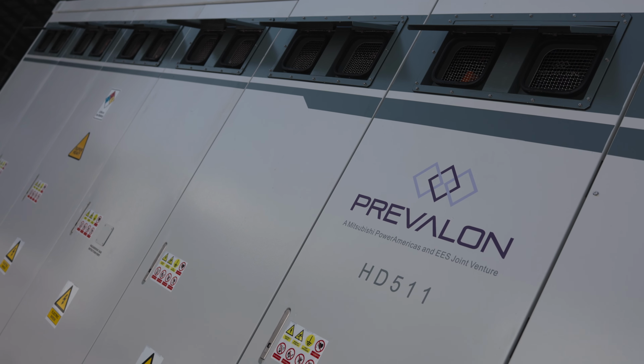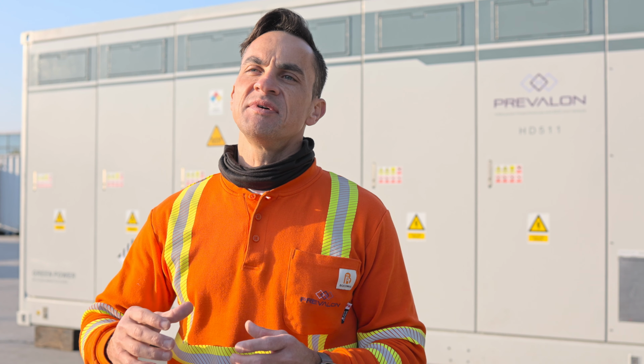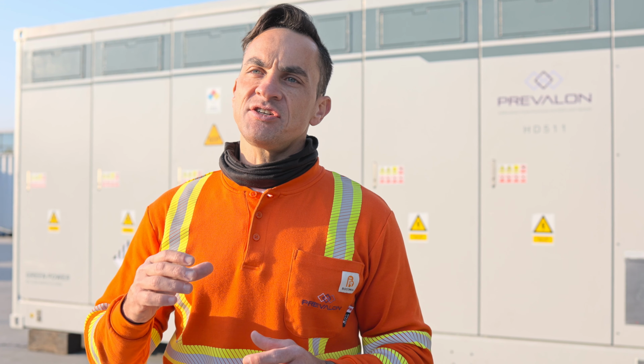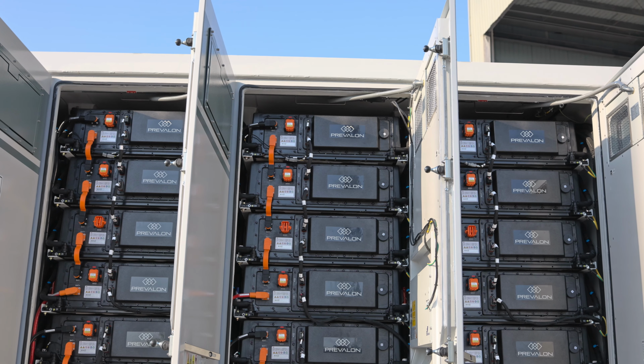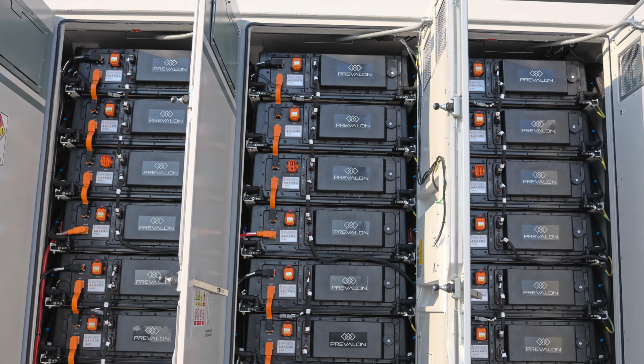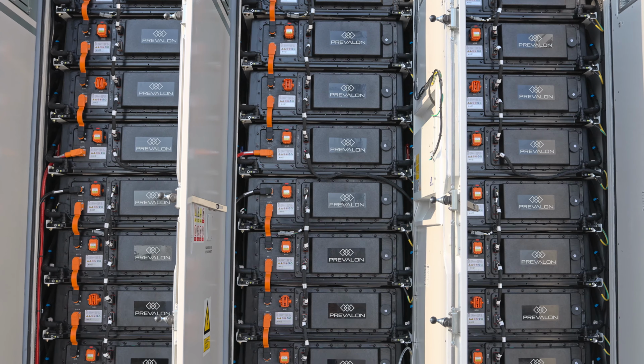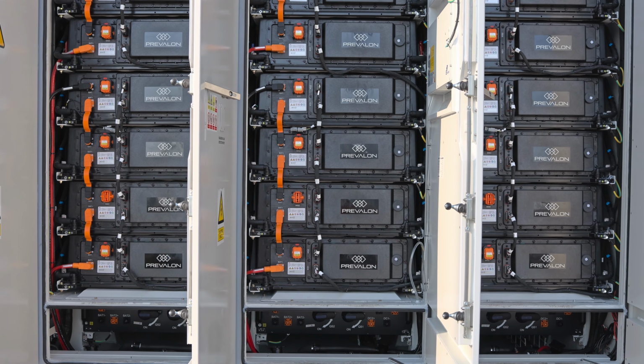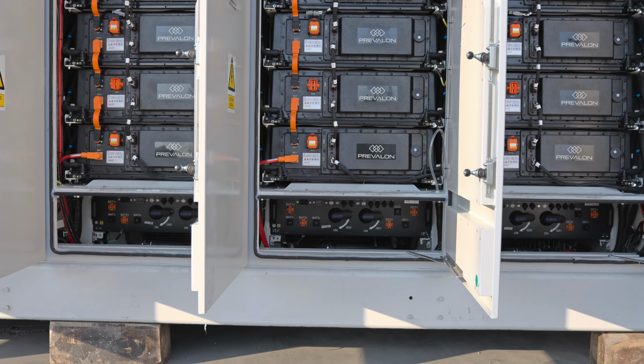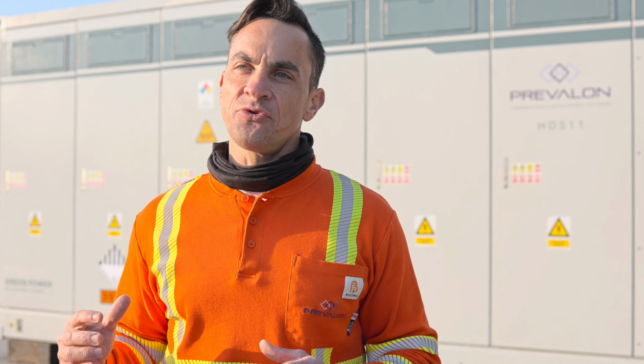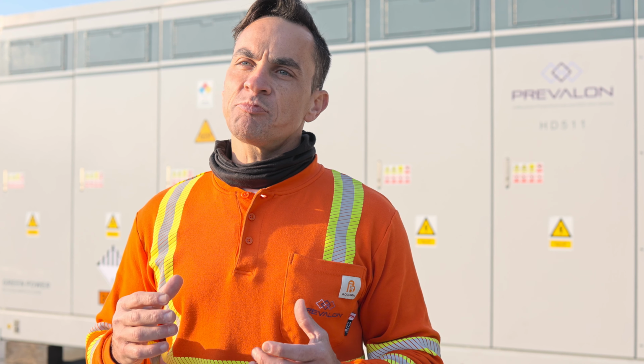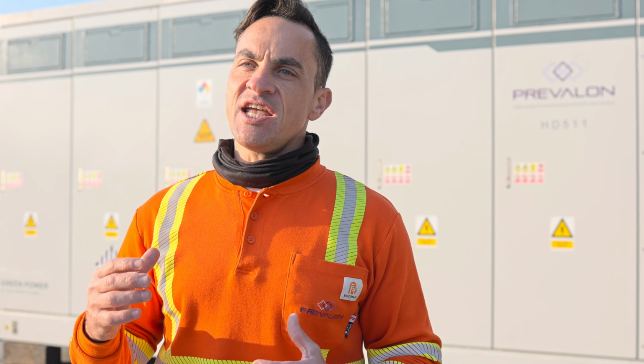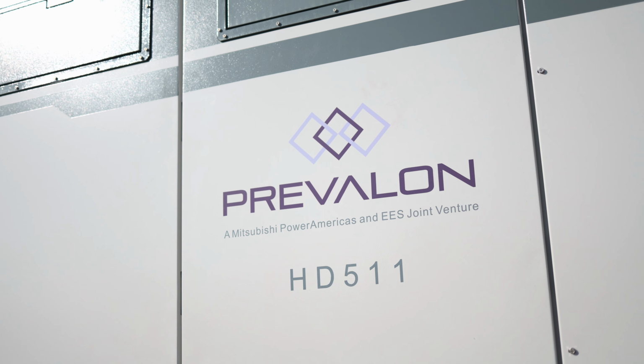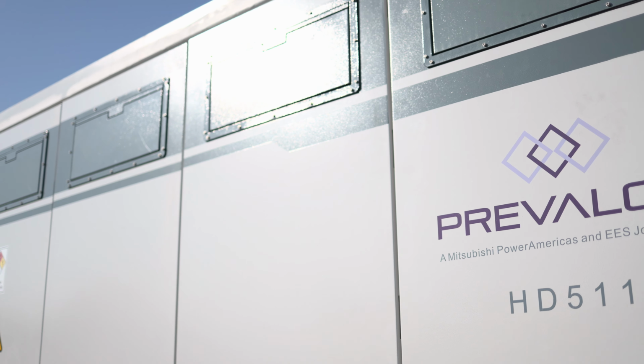This reduces auxiliary power requirements and allows us to extend the duration of backup power to the system in the event of an aux power interruption. Moreover, the size and location of the louvers is such that they enable passive ventilation through the enclosure as well. Upon self-venting, hot flammable buoyant gases will flow out of the enclosure through the top vents as fresh air enters the enclosure through the bottom due to the stack effect. These provide a degree of explosion prevention either during an extended auxiliary power outage or intake fan failure.